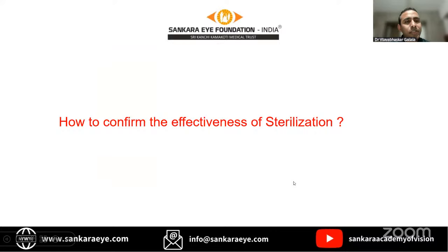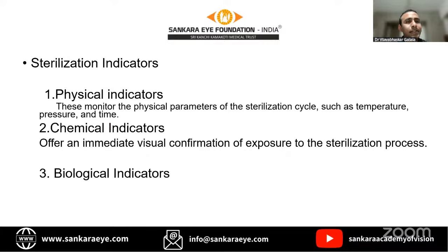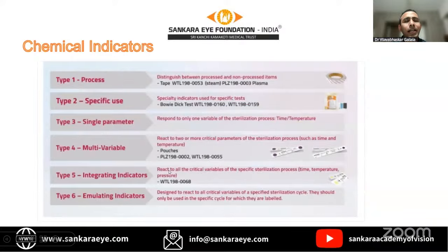So now the sterilization process is over. How to confirm whether the sterilization process is effective or not? For that, we have indicators. These are sterilization indicators. There are different types: physical indicators, chemical indicators, and biological indicators. These physical indicators are nothing but parameters like sterilization cycle time, how much temperature, and the pressure, and all those things. Whether this process is happening perfectly or not, we need to record all those physical indicator things. And the chemical indicators are the visual confirmation. There are different types of chemical indicators. When these chemical indicators are exposed to the sterilization process, due to the chemical reaction, there will be a change in the color of these indicators.